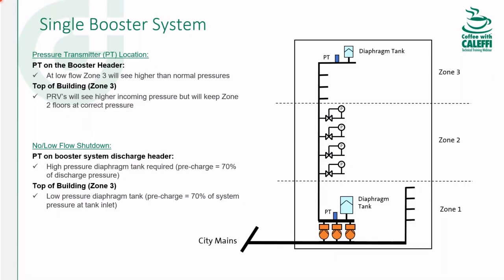Sometimes when the sensor is a good distance away from the booster, it takes some tuning at startup, some fine tuning and things like that. What I recommend is if you are going to go with a roof mounted sensor or remote mounted sensor, have a diaphragm tank close in proximity to the sensor because that enhances the controllability going back to the control signal there. In some cases, you'll have tanks at both locations if the pressure at the base is low enough because by having both tanks there, it actually makes your constant pressure system even more constant pressure and it also enhances your low flow shutdown. Everybody talks about no flow shutdown, but the best booster system design stops at low flow before it gets to zero. And the only way that's possible is to utilize diaphragm tanks.